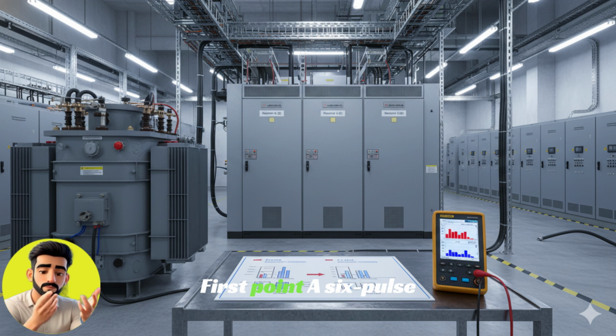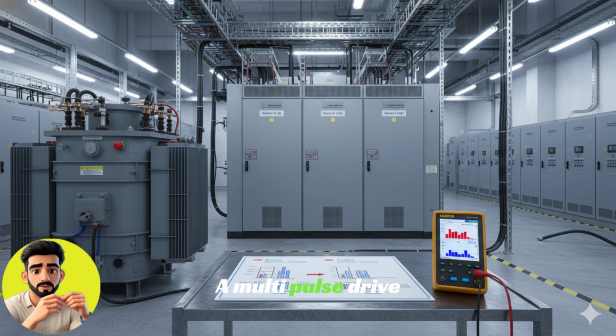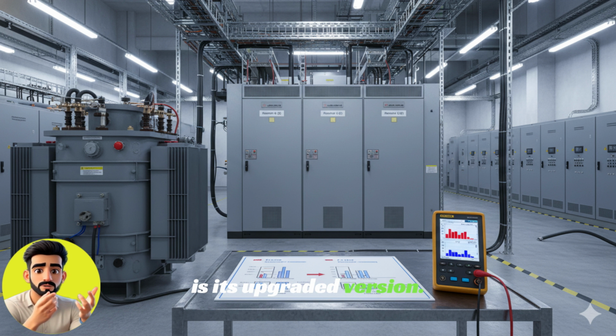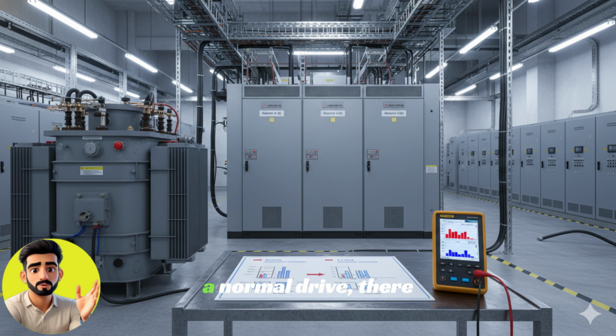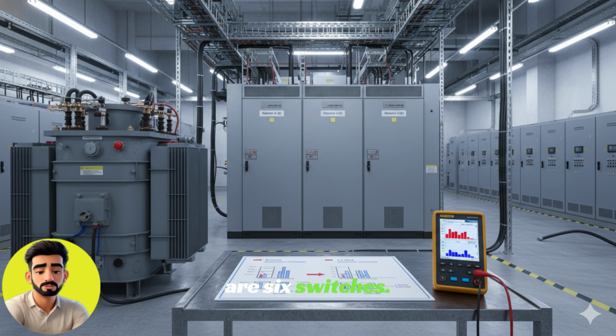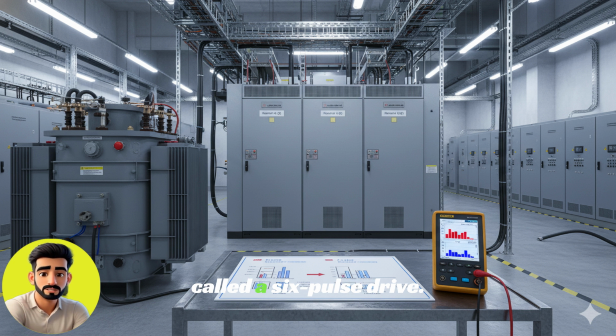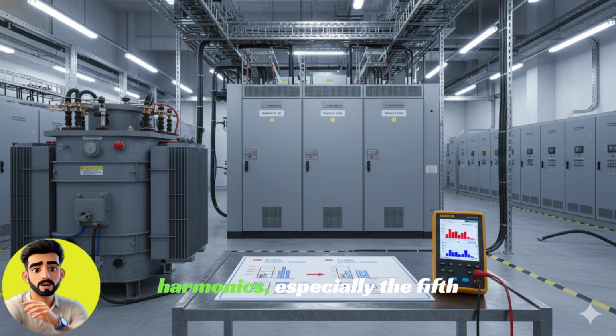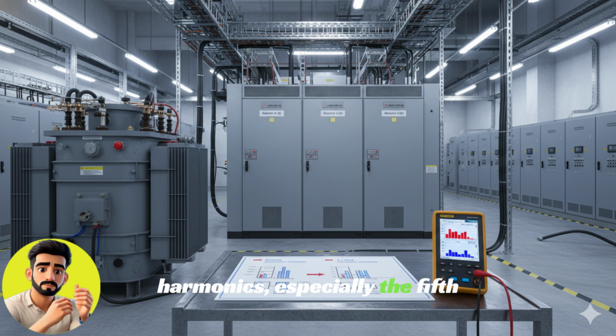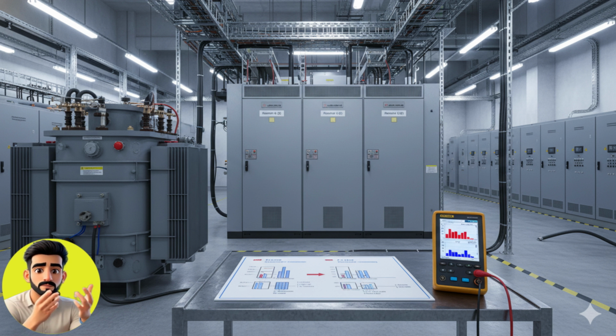First point. A 6-pulse is a normal VSD. A multi-pulse drive is its upgraded version. In the rectifier of a normal drive, there are 6 switches. That's why it is called a 6-pulse drive. This 6-pulse drive generates harmonics, especially the 5th and 7th harmonics. The multi-pulse drive solves this issue at the design level.